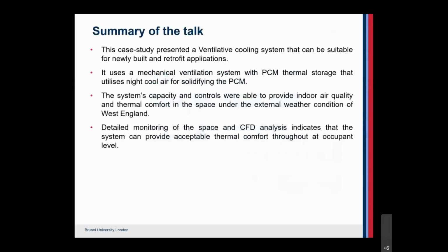So my summary is that this case study presented a ventilative cooling system. It was a retrofit application in this case, but it can be used in a new build. And as I said, it uses a mechanical ventilation system with PCM thermal storage, which utilizes the night cool air for solidifying the PCM. The system's capacity and control provide indoor air quality, and this is for the external weather conditions of West England. And also the detailed monitoring of the space and the CFD analysis indicated that the system could provide acceptable thermal comfort at occupant level. Thank you.